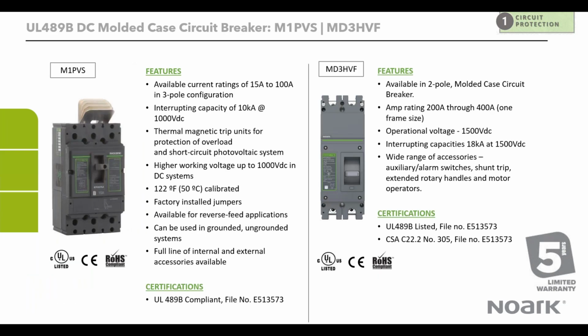So again, like I said, we've seen a lot of feedback in the renewable energies market. So we've got these DC breakers. This is rated up to 1000 volt DC, while the one on the right is 1500 volt DC. Again, because of the need for efficiency for inverters in the renewable energies market, we're finding a lot of applications that require this kind of DC voltage, and so we have this product available for that purpose.